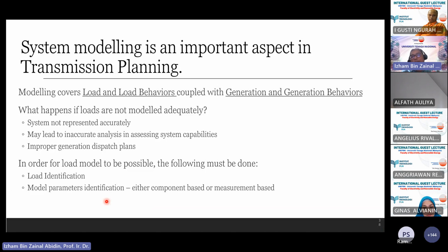However, once you have that dispatch schedule, you need to run through the network and check for its stability. Typically, when you run the network, you need to check for frequency, you need to check for voltage, and you need to check for thermal overload. Let's say I take an example for Malaysia. For frequency, I must make sure that it is at 50 hertz. It must not vary too high, and must not vary too low.